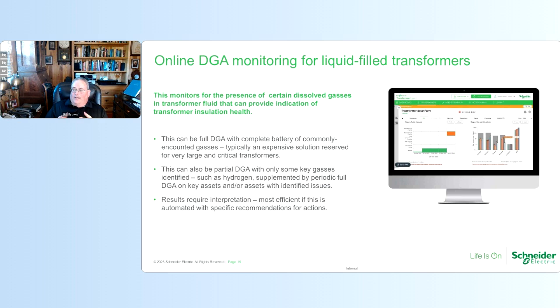In recent years, the value of a partial online DGA has become recognized. With partial online DGA, only a few or even one key dissolved gases are detected, which lowers the cost versus the traditional online DGA setup. However, the presence of the gases monitored indicates a potential issue and can trigger further investigation via oil sampling and lab analysis. Like partial discharge monitoring, DGA results require interpretation, and this is most efficient if it is automated with specific recommendations for remediation actions.